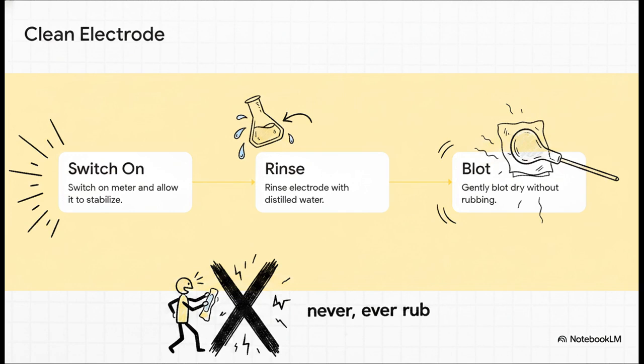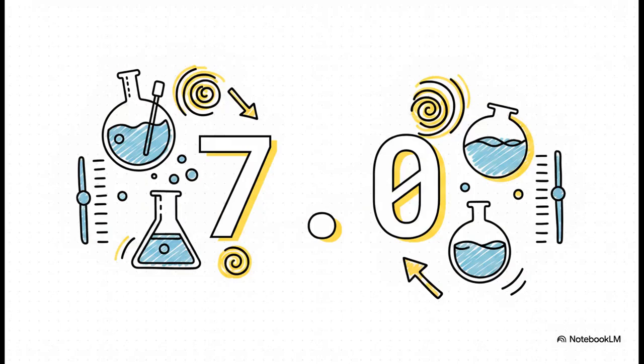The physical care of your equipment starts right away. First, switch on the meter and just allow it to stabilize. Then, thoroughly rinse the electrode with your distilled water. Now, pay attention to this crucial part. Gently blot the electrode dry. Notice I said blot. Never, ever rub it. It's a highly delicate glass membrane, right? It's not a magic lamp. Rubbing it creates a static charge that will totally scramble your readings, so a gentle blot is all you need. And that brings us to the absolute foundation of our entire process, 7.0.